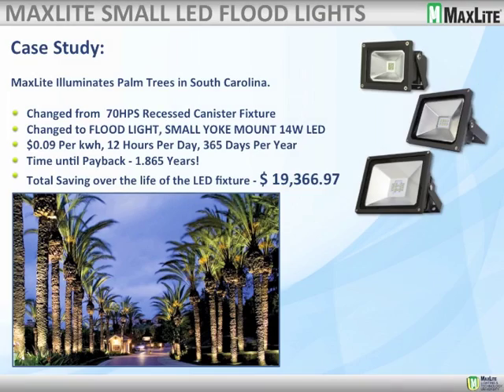Quick case study here. This was interesting. The sale was not motivated for energy efficiency, but for the maintenance of it, although the calculations I've done were all based on the energy. These were in the Carolinas, where they like to light up their palm trees, quite beautiful in the evenings. They had a maintenance issue of keeping all the lights lit all the time, so they chose LED for the long life. They took 70-watt high-pressure sodiums that were in recessed canisters in the ground, abandoned them, mounted the 14-watt flood fixture with a photo control at 9 cents a kilowatt, 12 hours, 365. They had a payback in less than 1.9 years with almost $20,000 in energy savings over the first 50,000 hours.